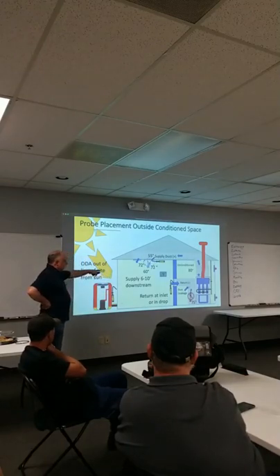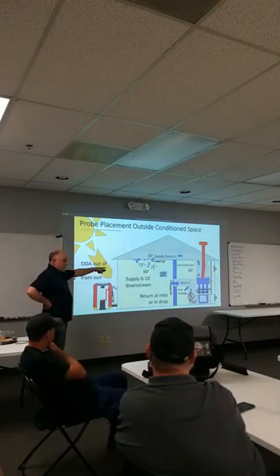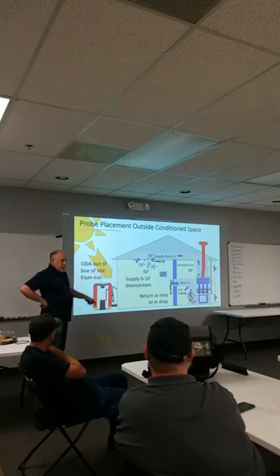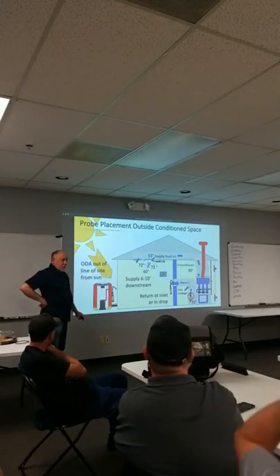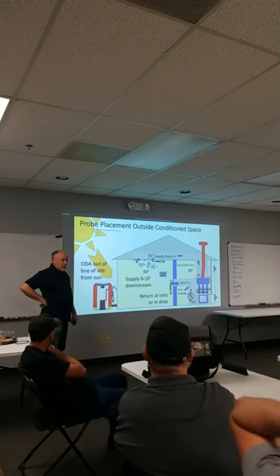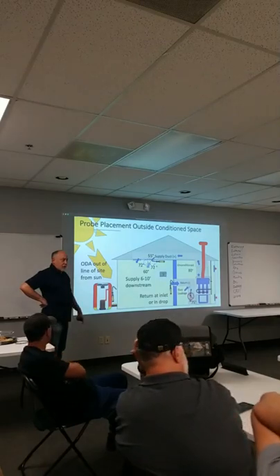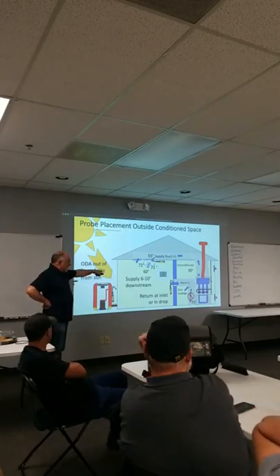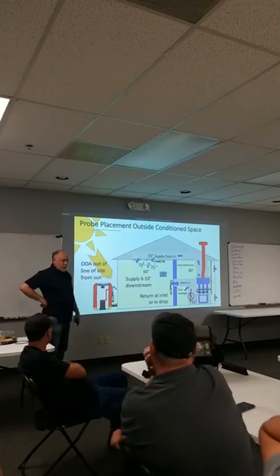And so what you wanna look at, a lot of times, when I'm walking into a space, mentally, I always look at the thermostat and sort of log what that is in my head. So when I look at my return air probe, if I see much more than a 1 to 2 degree difference, I'm starting to look for somewhere warm air is coming into the room, because whatever the space temperature is, that's what my return air temperature should be.